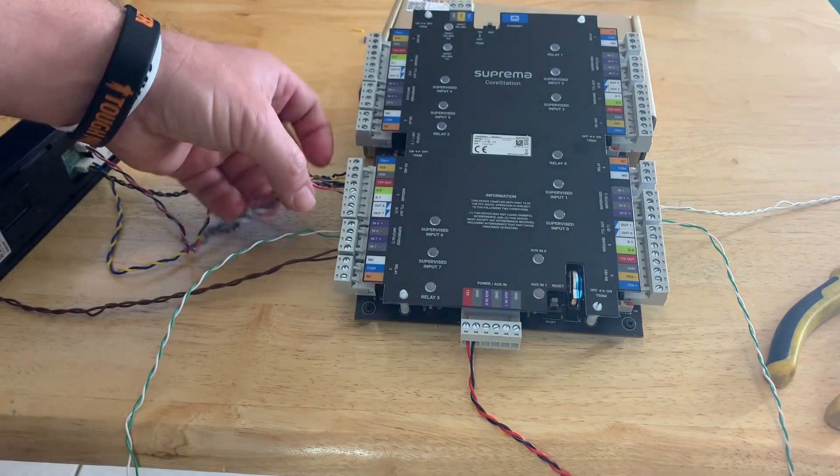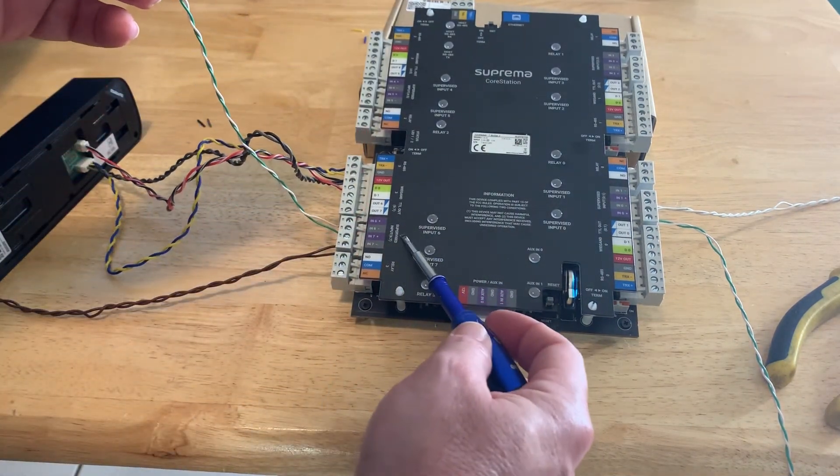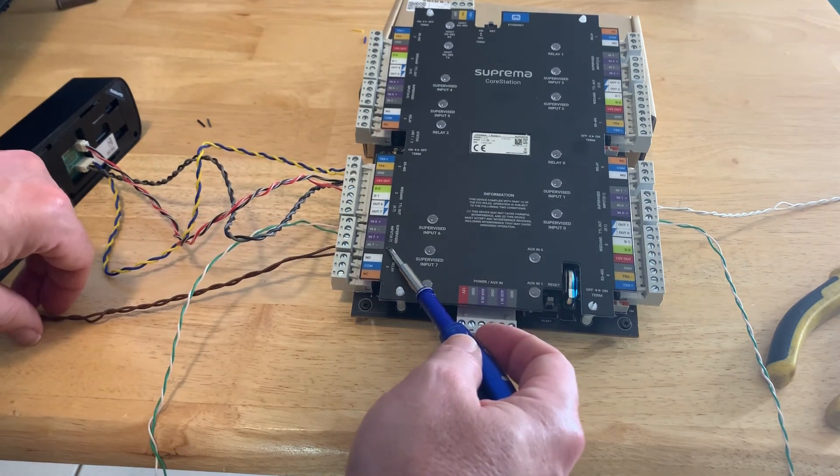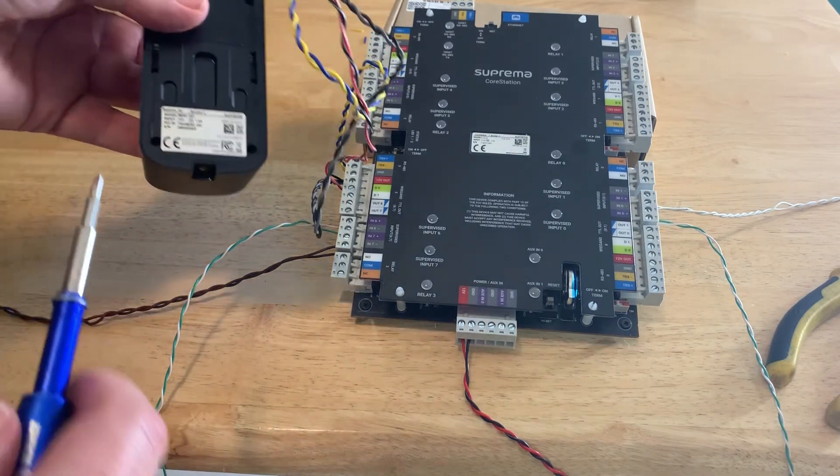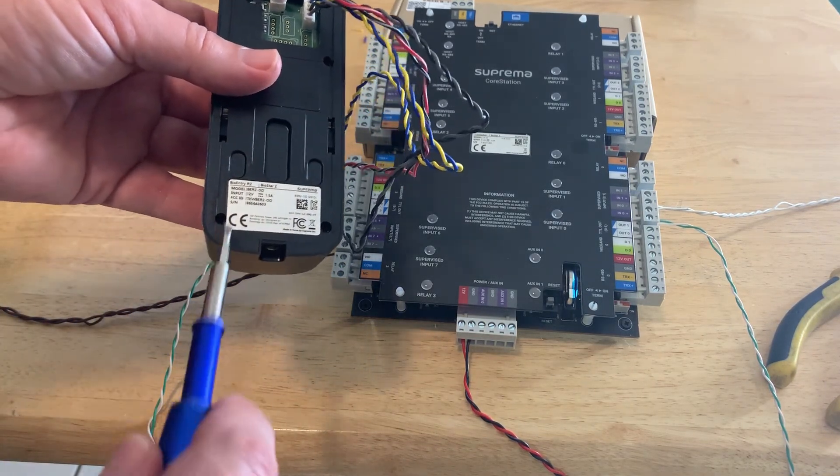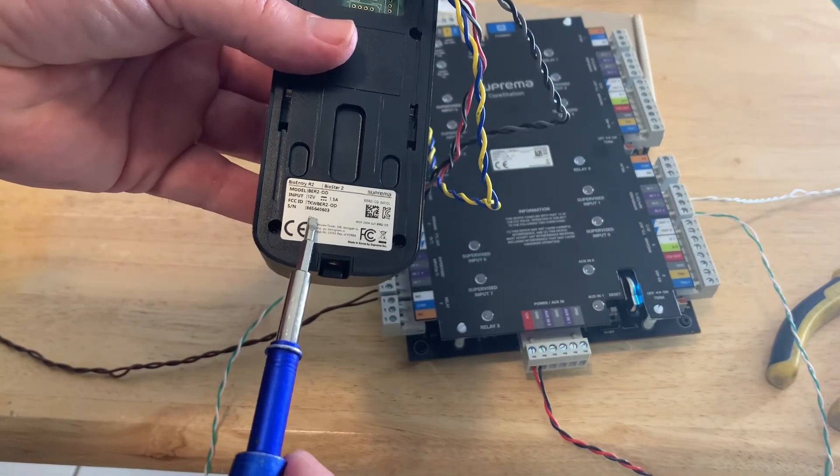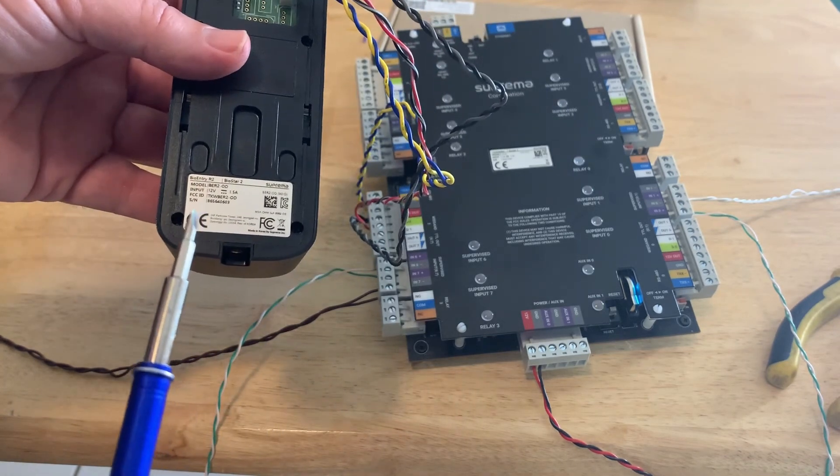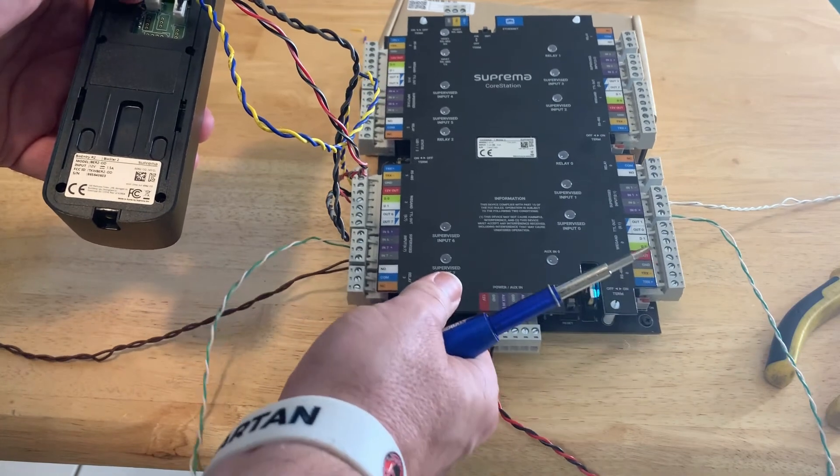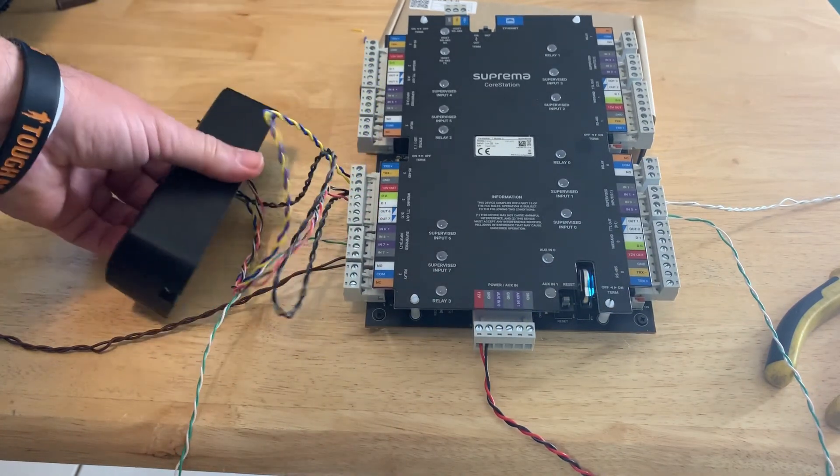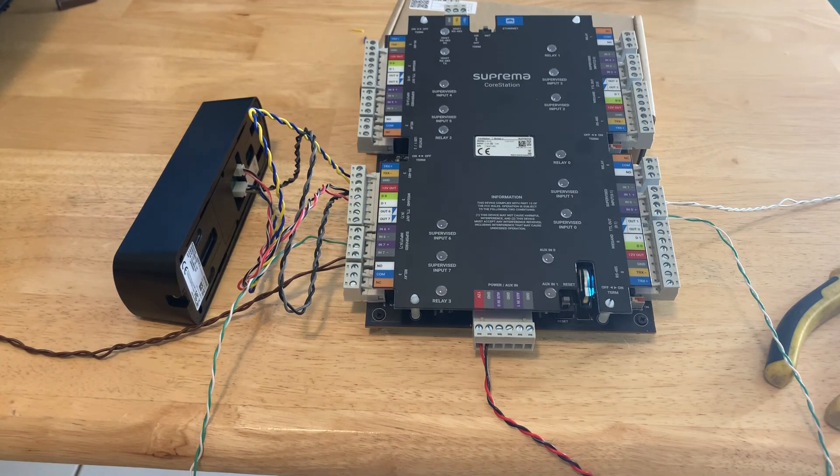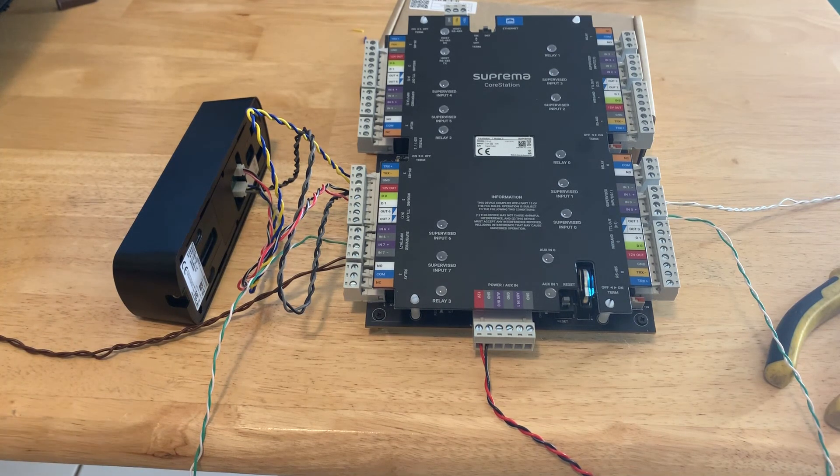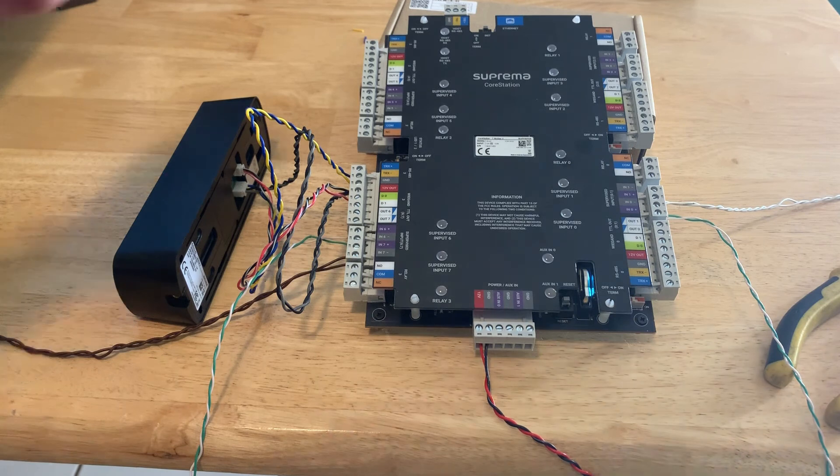And now with the rex I wired into port 6 and the door contact are wired into port 7. Now something to take note with any of our readers no matter which model you're working with, there's a serial number here on the back of the unit. It's good to document that serial number before you mount them and document where you mount them, because when you're inside BioStar 2 which is the software you use to add them in, you see them by serial number. So if you have multiple readers of the same model type you can't necessarily tell them apart. So if you document it beforehand just a best practice to do so.